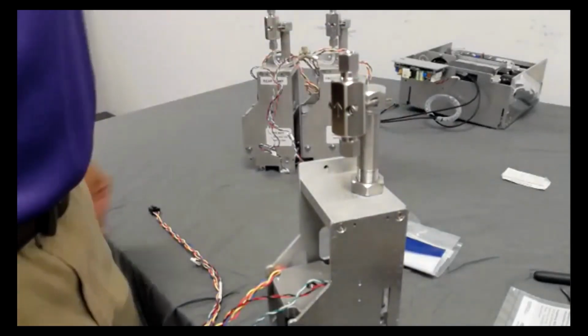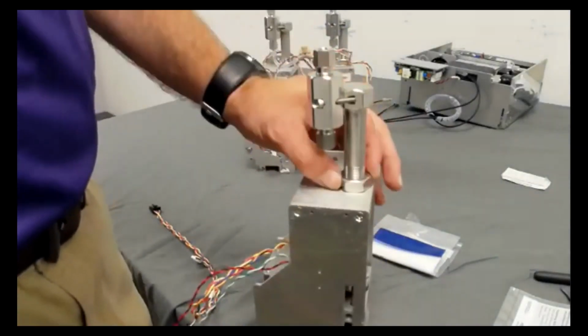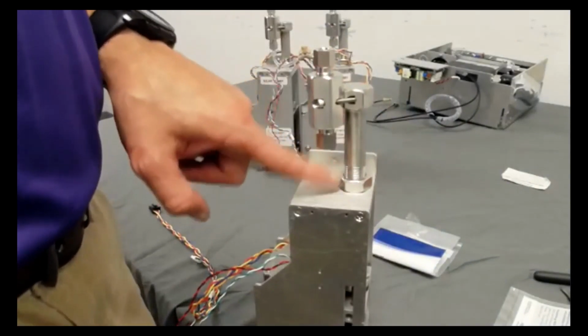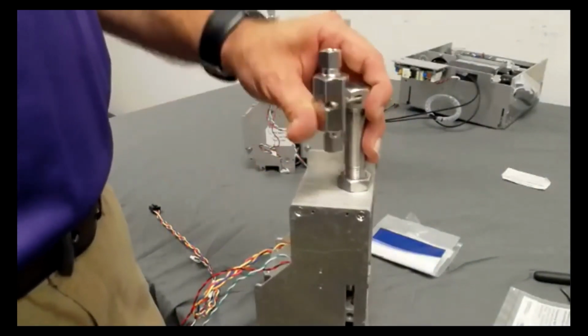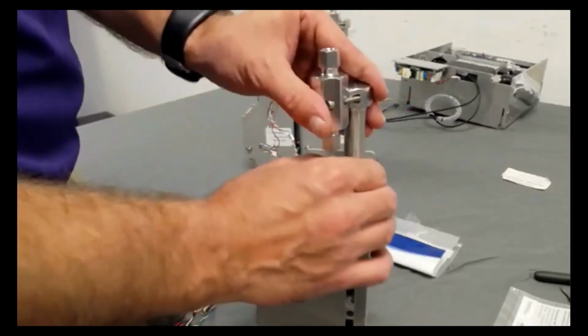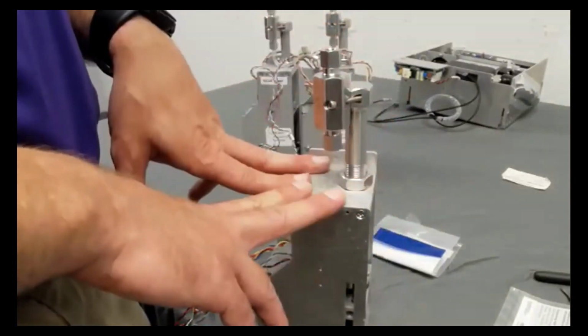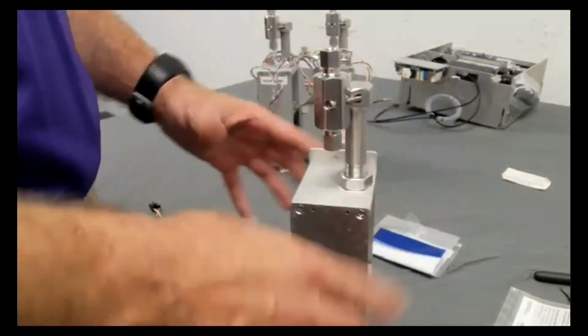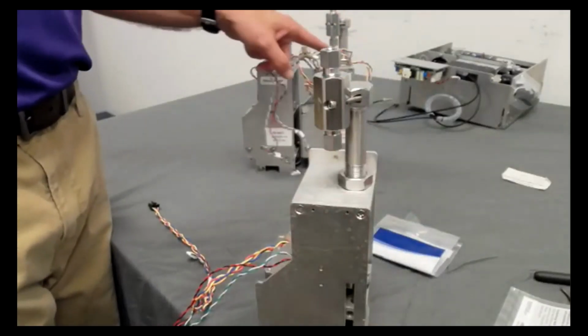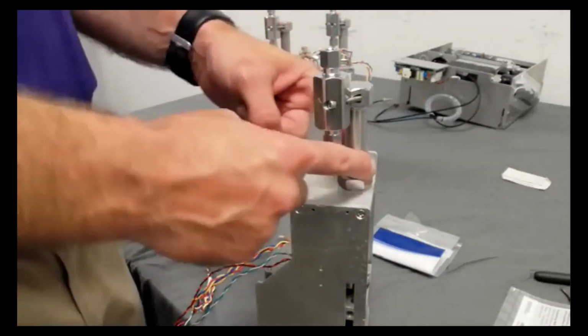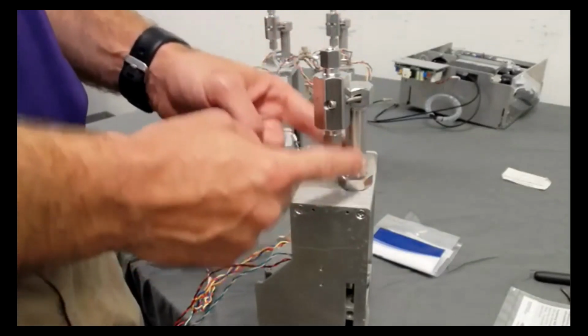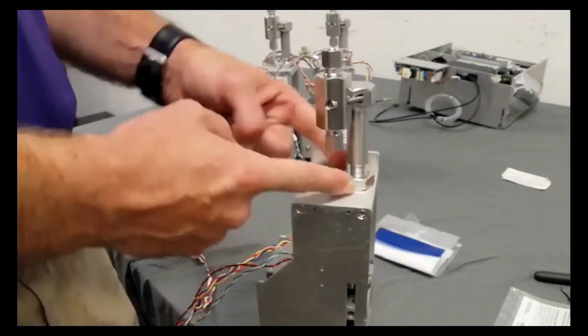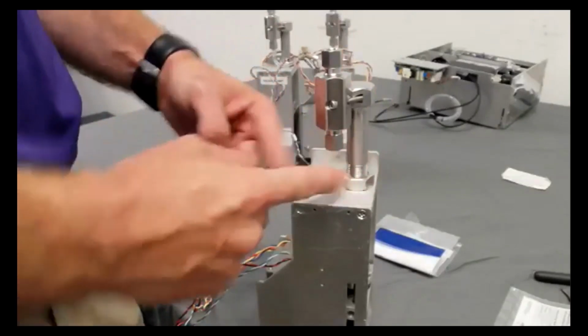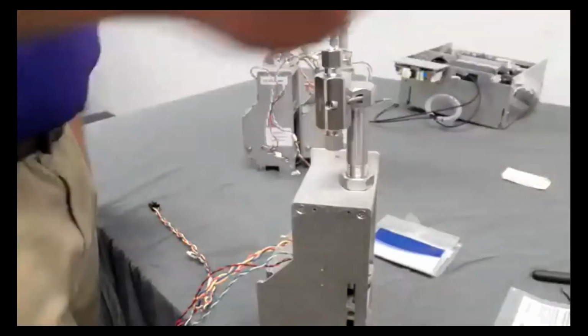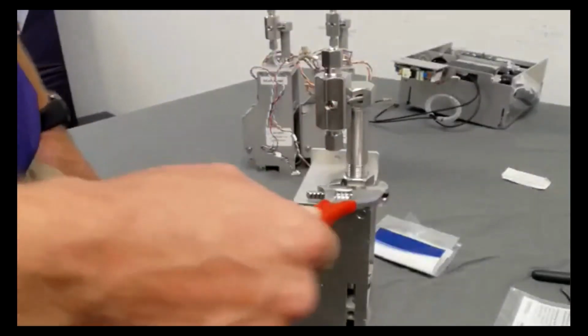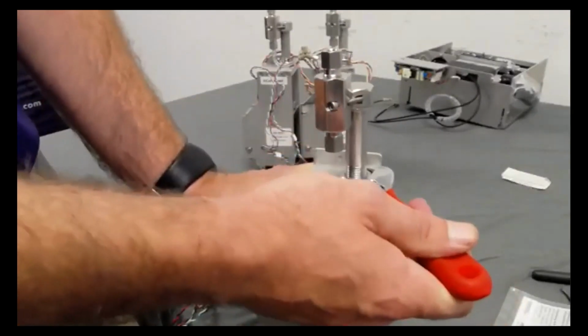Now I'm ready to change the pump seal. So this is a jam nut. It's a tightening nut, and that's supposed to keep this cylinder from moving. Now, this is my example pump, so everything's a little bit loose. When you work on an actual pump like these that we took out, there's going to be Loctite. Loctite's a strong industrial adhesive, and we use a thread locking Loctite on this. So you're going to take that crescent wrench I told you to have and loosen your jam nut.